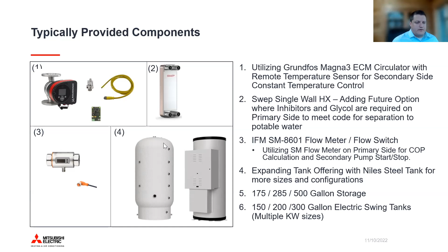A lot of these things we talked about really have a play with the utilities. One of the biggest things we see across the marketplace is everybody wants to know how efficient the system is, how it's operating, to gain that trust in using a heat pump for domestic hot water. So what we've developed is a control system that pulls in all that data across the system and can send it either to a cloud-based platform, or also to your BMS or anything else like that. It has some built-in load shifting and demand response.